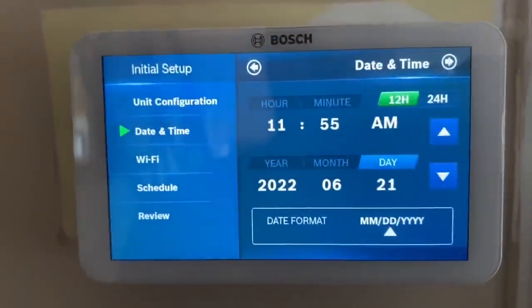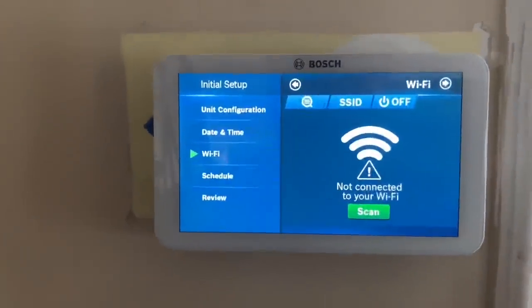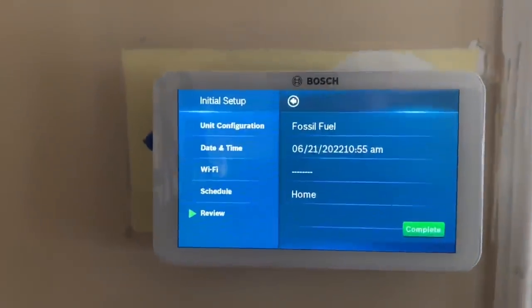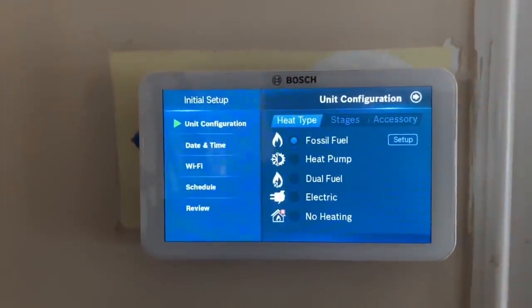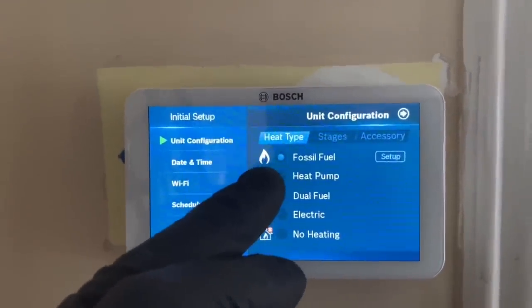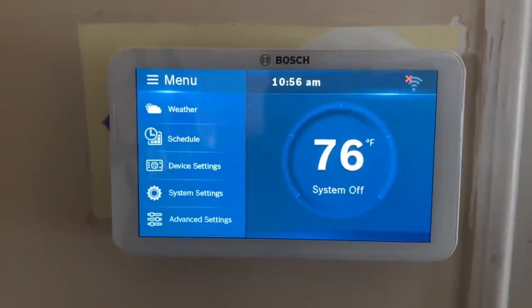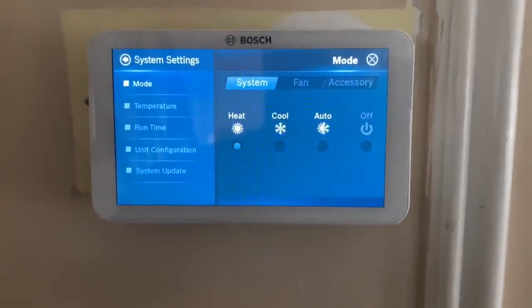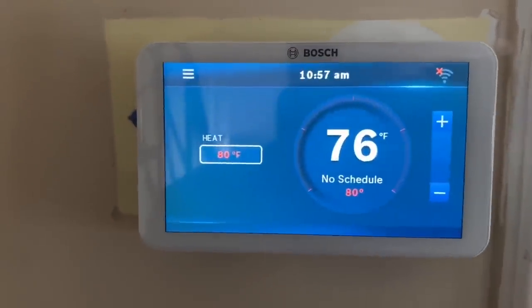We're going to set the date and time — 11:55 AM. Hit next, do Wi-Fi later, and for now no schedule — let the homeowner figure that out later. We're doing fossil fuel configuration — that's correct because it's R, H, and W. Configuration review: perfect, complete. I want to test the heating now, so we're going to go to system settings, mode, set to heat. Let's raise the temperature to 80 and see if the zone on the boiler turns on.